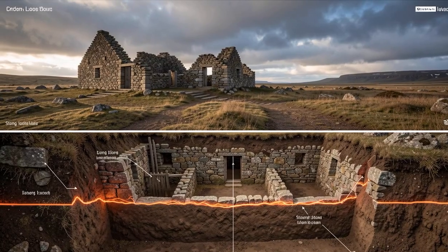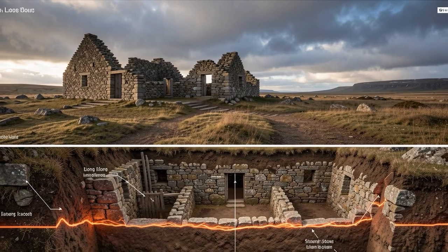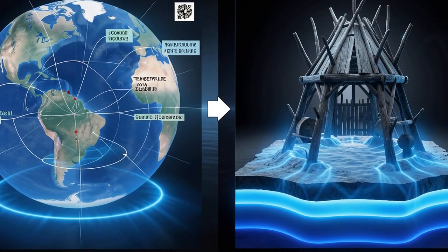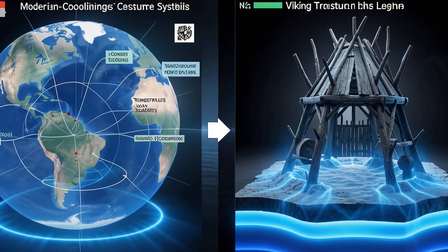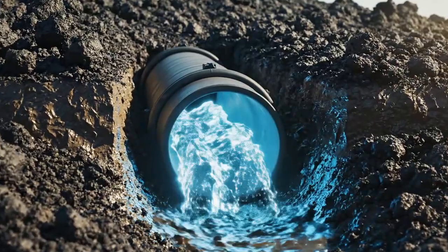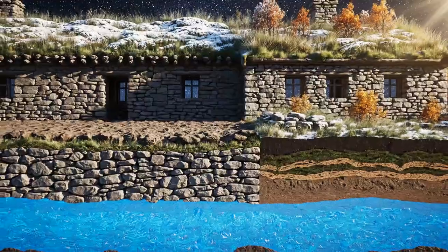If the water table in your area sits within 2 or 3 feet of the surface, common in low coastal areas, river floodplains, and regions with heavy clay soil, the ground at pipe depth does not hold a stable temperature through the summer. It follows the water table instead, which responds to rainfall and season far more quickly than deep, dry soil does. The ground around the pipe stays too wet and too thermally variable to act as a stable, cold reservoir. In those conditions, the earth tube loses most of its cooling potential.